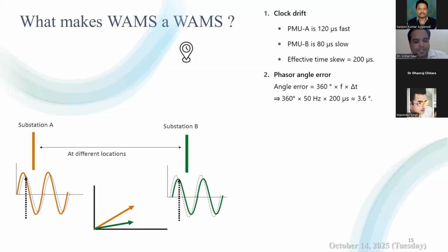To understand the importance of synchronization, consider two substations, substation A and substation B. They are located far apart, so their voltage waveforms look independent, and phasors are measured using the local clock in this case. Even a small clock drift between PMUs can lead to large measurement errors. For instance, PMU A might be 120 microseconds fast and PMU B might be 80 microseconds slow. This creates an effective time skew of 200 microseconds.